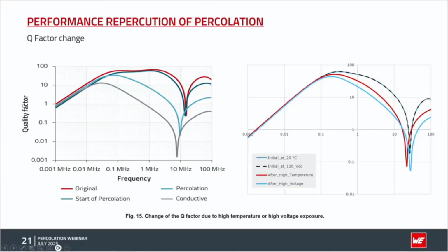On the other hand, what was interesting is that when we used the same competitor part and compared high voltage and high temperature, we found that the curves change for both scenarios. So we have one part exposed to 120 volts. We apply a round of shots up to 120 volts. We put it in a real application, and due to our voltage specification, we guarantee that the part was performing well. But I increased the voltage a little with some peaks of 190 volts. And then with some peaks, the curve changed, as we can see here in the light blue color.